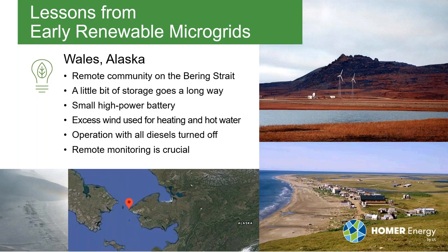A similar system in an even more remote village — where humans first set foot on North America — also used innovative storage. A small nickel-chemistry (today lithium) battery providing just 15 minutes of storage was enough to be much more aggressive about turning off the diesel, since you had a bridge to restart it. It also used excess wind for heating. A really important lesson here was the need for remote monitoring — the system was down for six months and we didn't know.